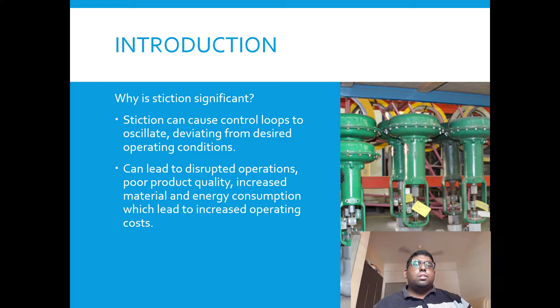There have been several studies that have indicated that about 20 to 30% of control loops oscillate due to valve non-linearities, where the prevalent source of non-linearities is stiction. Valve stiction causes limit cycles, which are oscillations that are periodic finite amplitude instabilities that lead to variability in product quality, accelerate equipment wear, and lead to system instability.